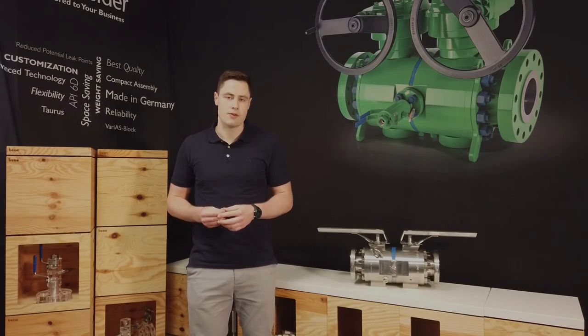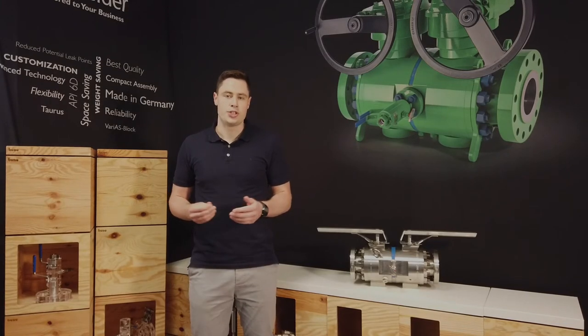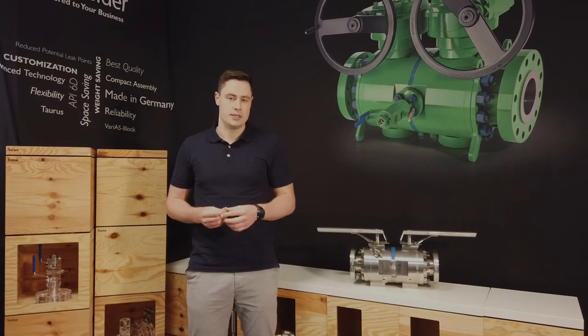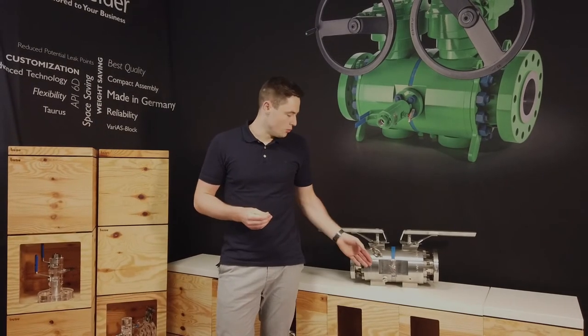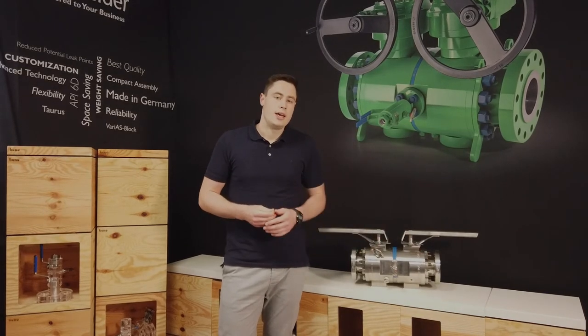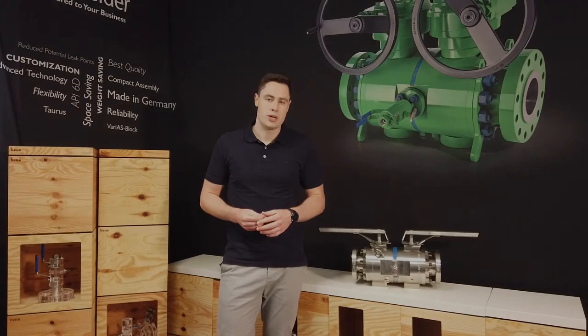This definition describes the use of three independently operating valves — two for isolation and one for venting — which are incorporated in a single valve body. Our Taurus-series DBB valves, with two valves for isolation and one separate vent valve for venting, match these requirements.